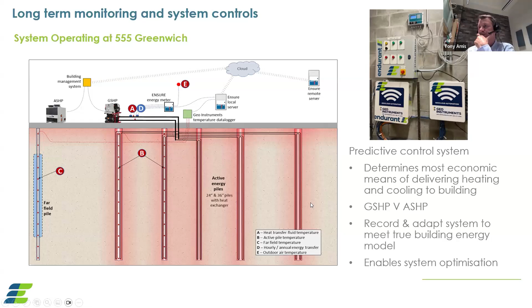So this is a visual of what we see. We can dial into the system, and we get live data from what's going on. And the crucial temperatures that we look at are these temperatures here, the leaving ground temperature, so that's flowing into the heat pumps, and then what's entering the ground temperature. And what we're generally looking for is a delta T of between 5 and 10 degrees Fahrenheit.